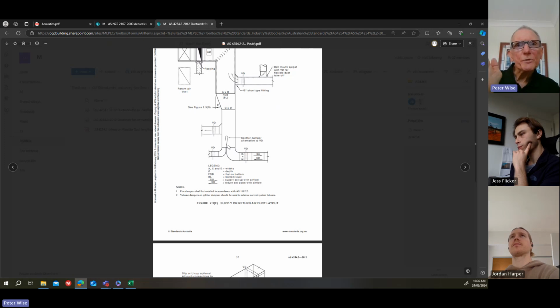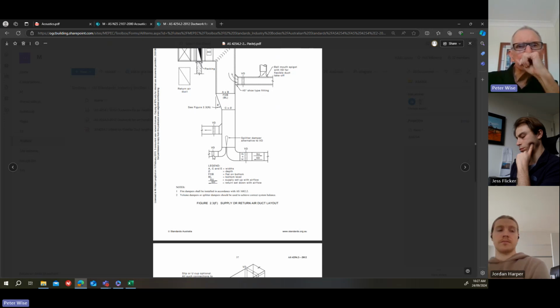But the way a splitter damper works, usually it's just a piece of steel plate, and it has a connection which goes to the outside of the duct with a quadrant on it, like any other damper. So you can turn it. Sorry, you can pull it. It's a push-pull. You have to pull it out and then lock it when you get the desired flow in each direction. And you could do it as well as volume dampers to get the coarse control, and then the fine control with the OBDs in the ductwork.